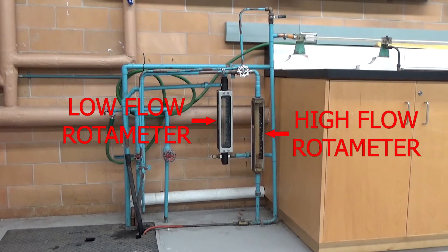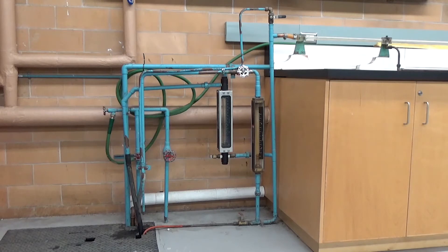If I want to use the other rotameter, I make sure the first valve is closed and open this valve here, which allows water to flow up through this tee through the bottom of the meter. Again, the more water that flows around the float, the higher the float comes to steady state and we read directly off the scale how much flow we have. If I want to discharge all of the line completely without going through any of the meters, I can just open this globe valve down here and the water will flow directly into the drain.